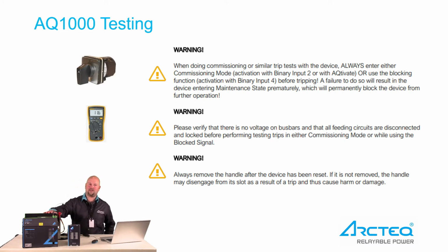So the device can be tested up to 100 times. If we consider other available units, a typical arc quenching unit cannot be tested. It can be installed, it can be left, but it cannot be tested completely. This single shaft, the only single shaft in the world, means that all 3 phases have identical timing. They close at exactly the same time, which makes the short circuit more pure.